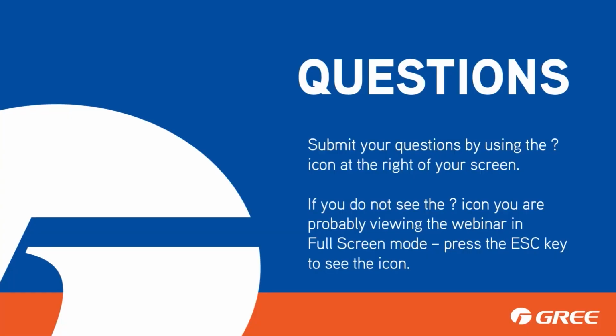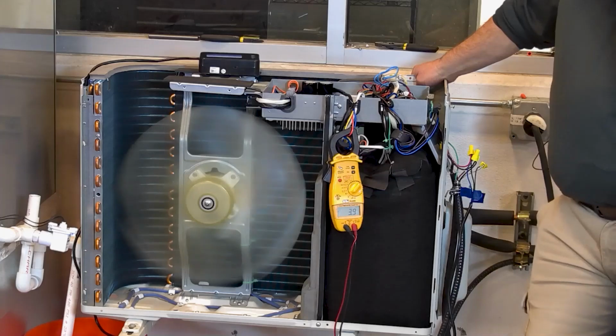What makes a single zone go into F0? He says he has one installed 3 hours away. As soon as they turned it on to heat, it went to F0. And they put gauges on, it matches the PT chart. What is next? Could be an indoor ambient or indoor coil temperature sensor failure. Yep. We know it's the coil, but I tell them to check both. It's the same plug. And the other thing is, if you need one, you're getting both. Right? Yep. So, again, use that ohm chart. You should be able to easily test that.